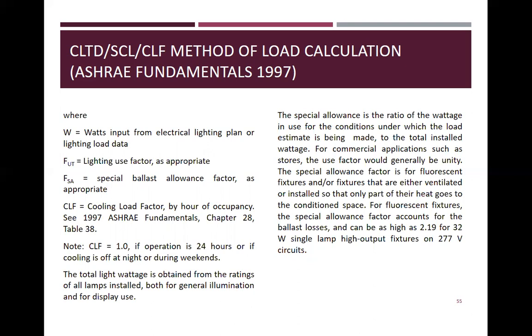The total light wattage is obtained from the ratings of all lamps installed, both for general illumination and for display use. The use factor is the ratio of wattage in use for the condition under which the load estimate is being made to the total installed wattage. For commercial applications such as stores, the use factor would generally be unity. The special allowance factor is for fluorescent fixtures and/or fixtures that are either ventilated or installed so that only part of the heat goes to the conditioned space.